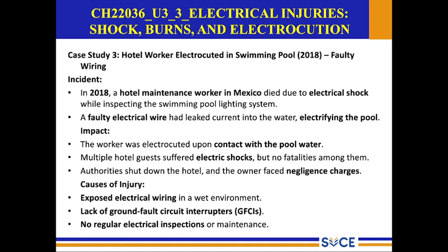Then there is another case study, the hotel worker electrocuted in a swimming pool in 2018, caused by faulty wiring. A hotel maintenance worker in Mexico died due to electrical shock while inspecting the swimming pool lighting system. A faulty electrical wire leaked current into the water, electrifying the pool.